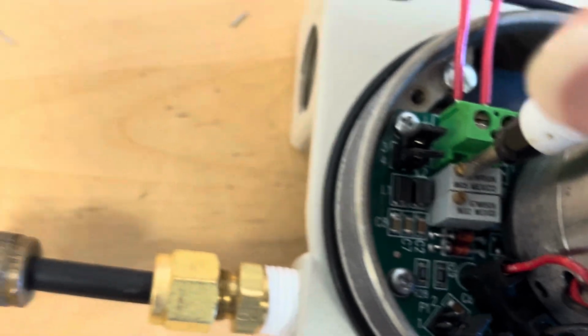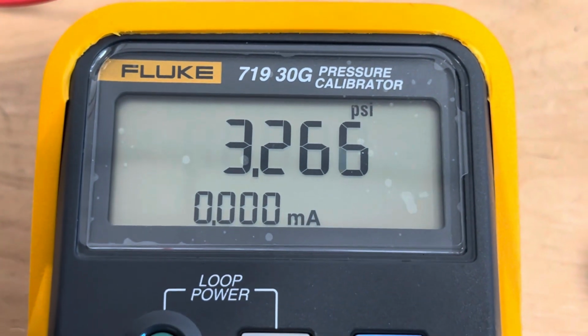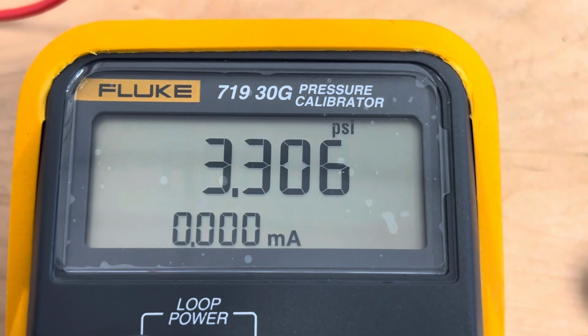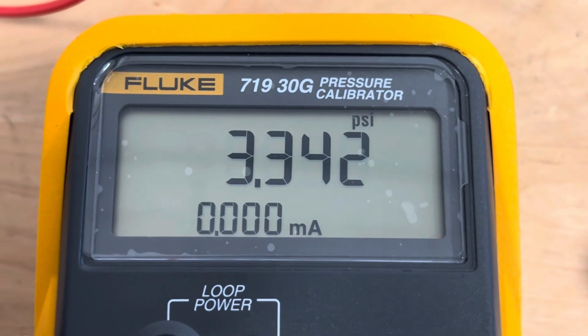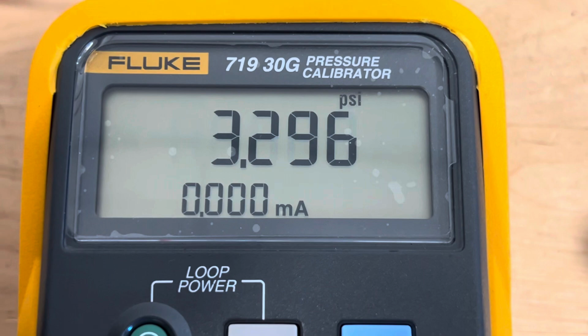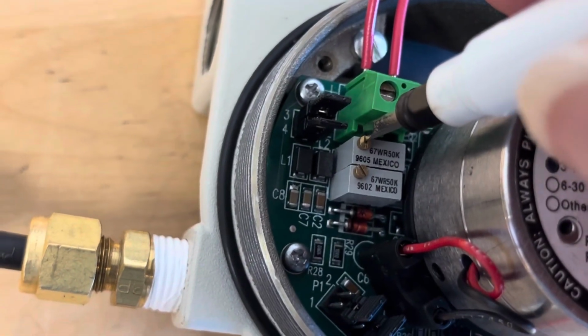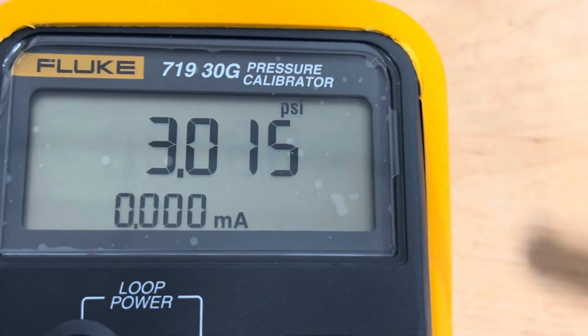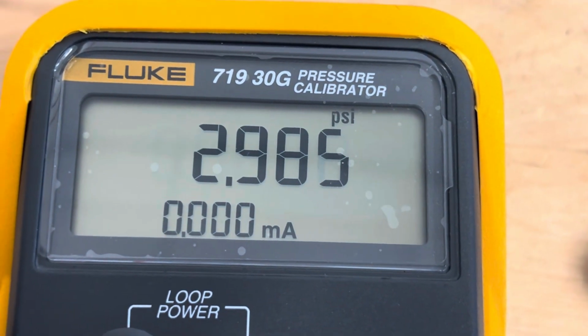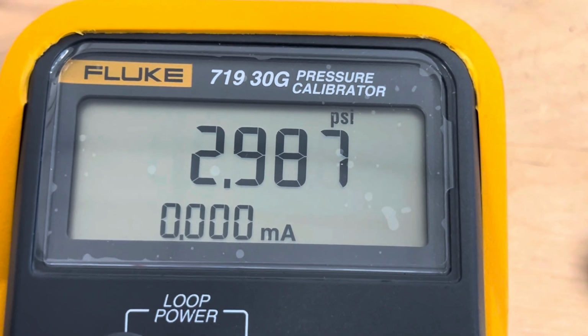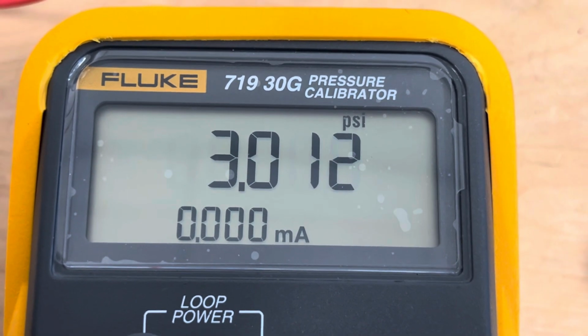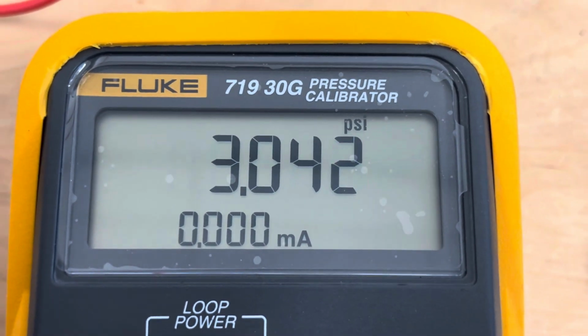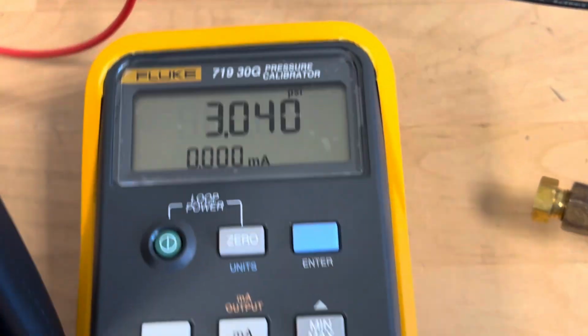And as I turn the potentiometer here, you can see the PSI changing. So I'm going clockwise and it's getting further out. So I'm going to go counterclockwise to bring it down. Continuing to turn this screw here on this potentiometer. And all right, I am at 3.042. That's close enough. Now let's do the span calibration.